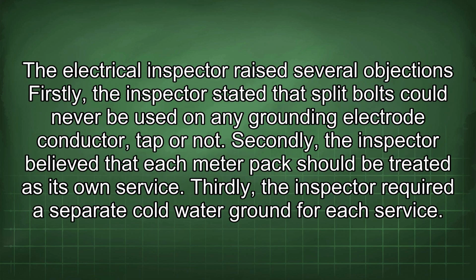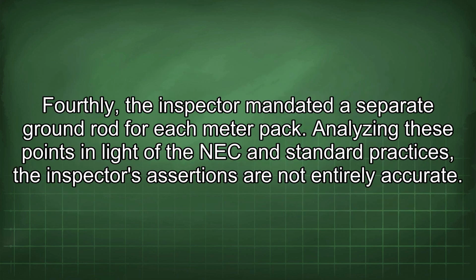The electrical inspector raised several objections. Firstly, the inspector stated that split bolts could never be used on any grounding electrode conductor, tap or not. Secondly, the inspector believed that each meter pack should be treated as its own service. Thirdly, the inspector required a separate cold water ground for each service. Fourthly, the inspector mandated a separate ground rod for each meter pack.